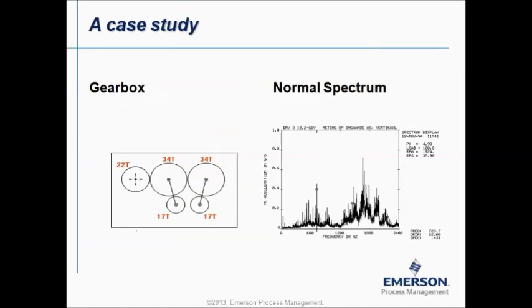Now, if this is a little bit too theoretical, let's take a look to a live example. We have a gearbox with five shafts, one input shaft with 22 teeth connected to a second shaft with 34 teeth, this one is connected to another one with 34 teeth, and those two shafts are connected to smaller shafts with 17 teeth, and those two shafts are the output. So, one input and two output shafts. This is the spectrum measured on the input, and as you see there is quite a lot of energy in the spectrum, but also a lot of noise, so something bad is going on, but it's rather difficult to find the reason, the root cause of all this energy.